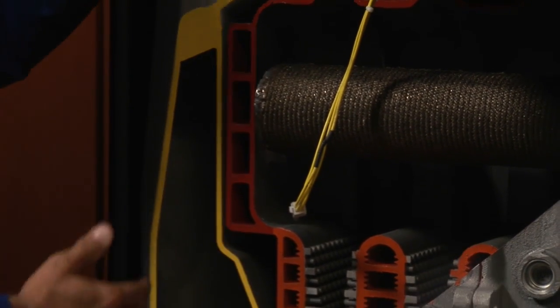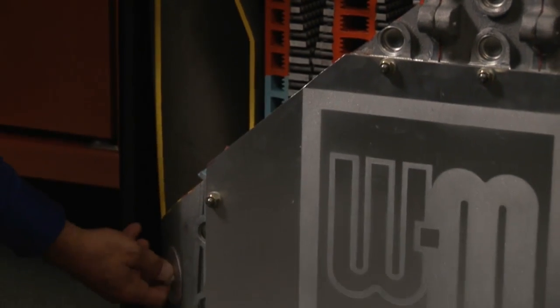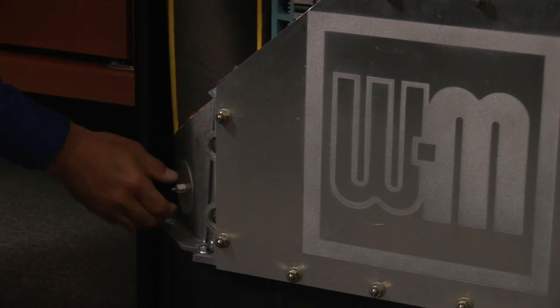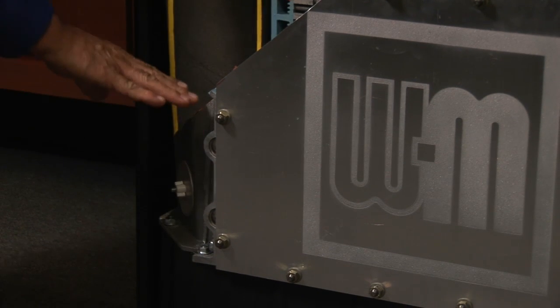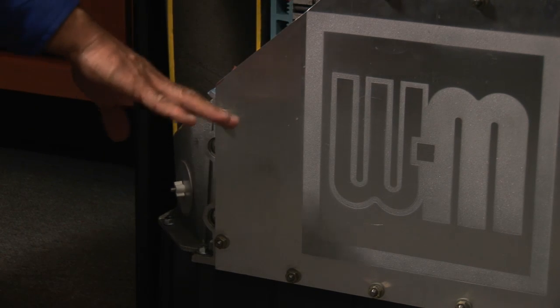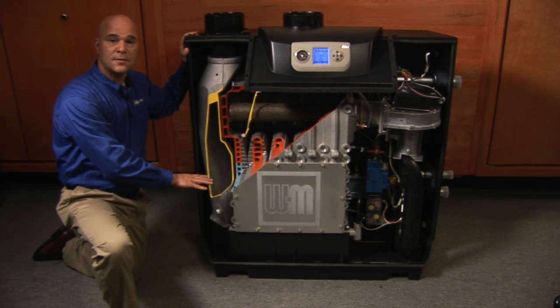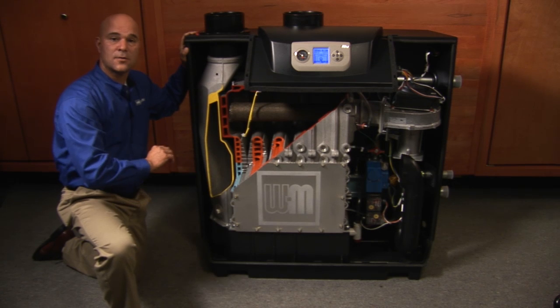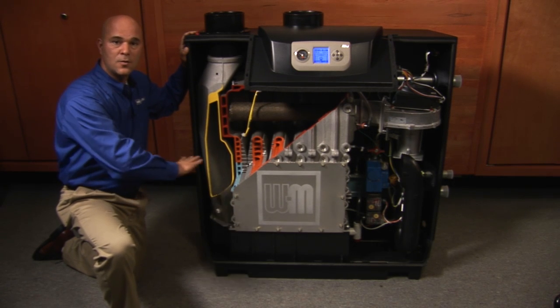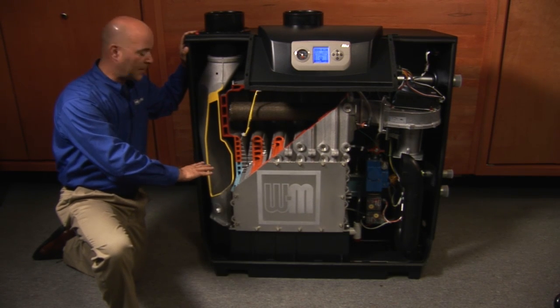This is cast aluminum, and there's a clean out right here on the base. You can take this out, and it gives you a view down into the condensate base, and you'll be able to see what's going on down the condensate base. It's also where you can take and hose that area out and make sure your condensate base inside the boiler is clean.